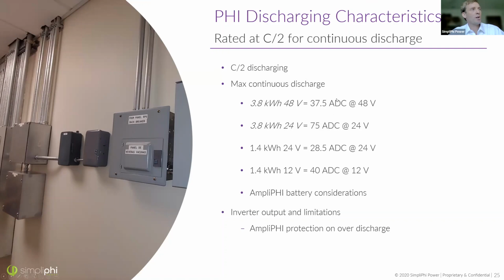But the max discharge rate is similar to the max charging rate for these batteries. It's C/2, which is 37.5 amps for our 48-volt battery, double that for the 24-volt battery, etc.